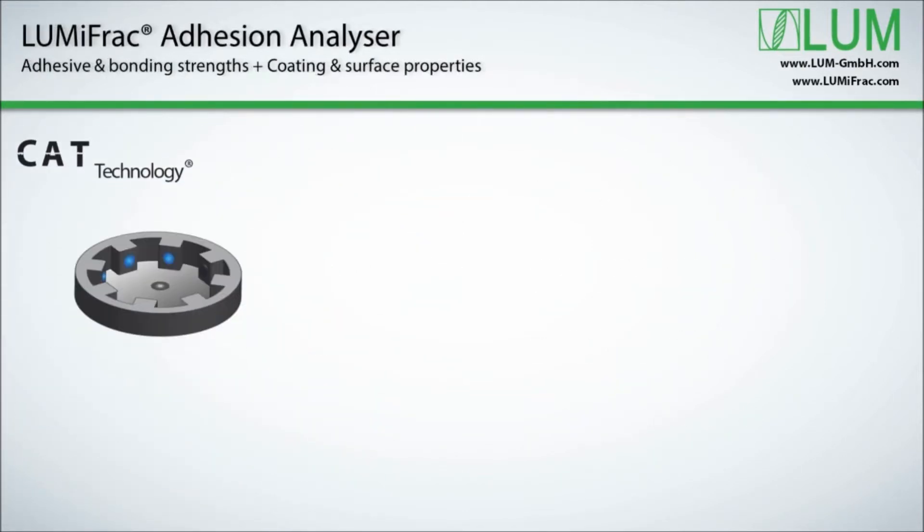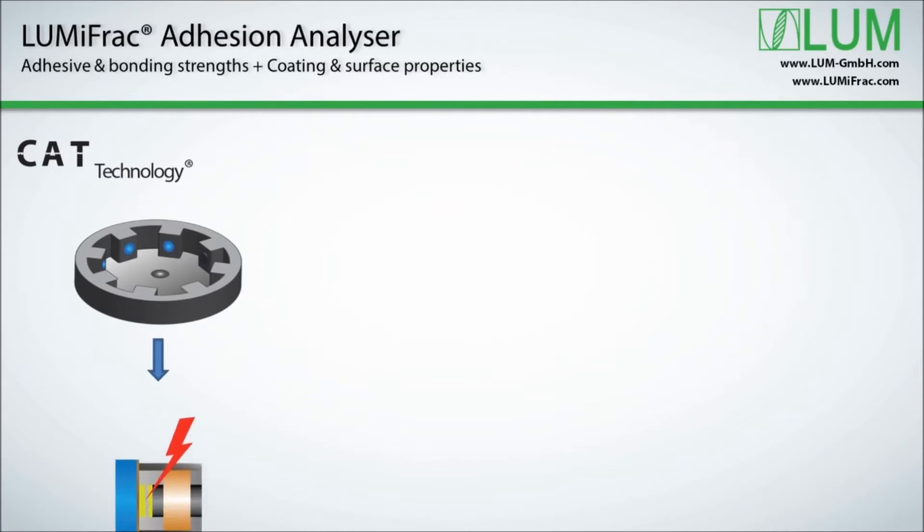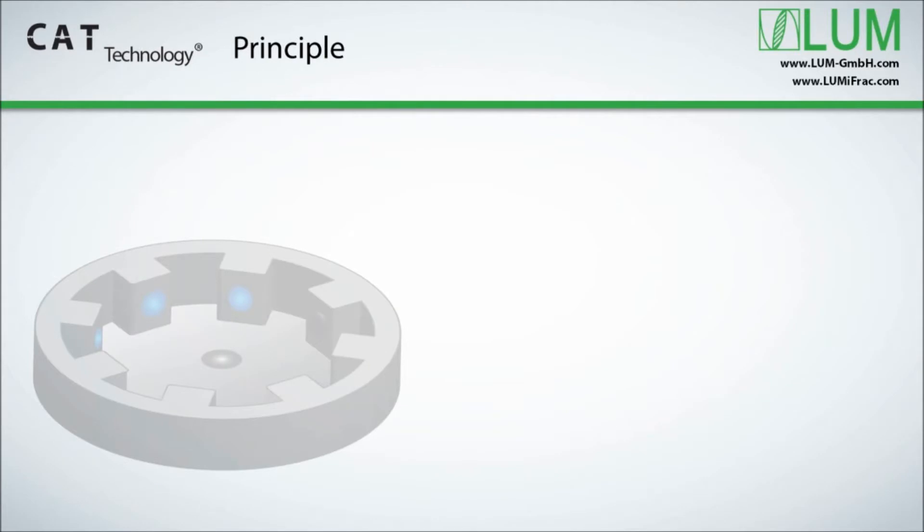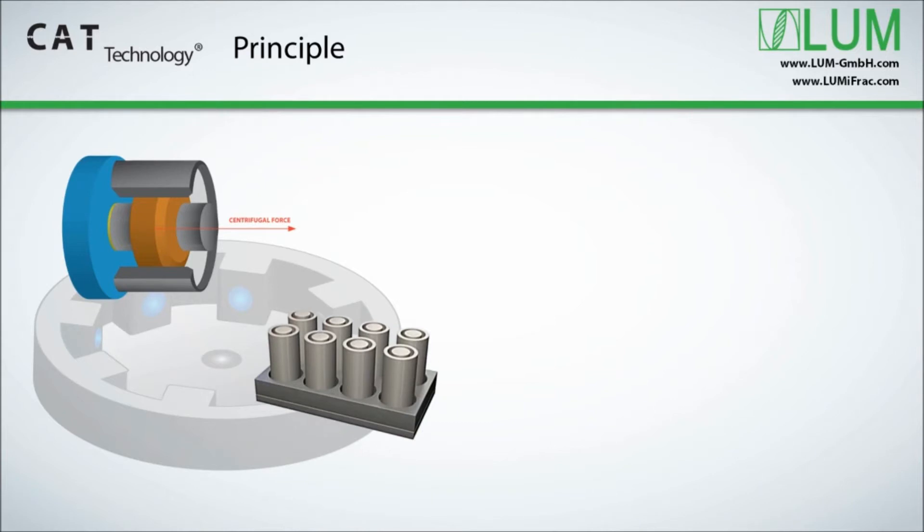We will give you a short introduction in CAT technology and sample preparation, present a selection of measurement results, and show you step-by-step how easily you can operate this analyzer. Our new multi-sample measurement principle CAT technology determines adhesive, bonding and composite strength by detecting automatically the critical failure load of up to 8 samples tested simultaneously.